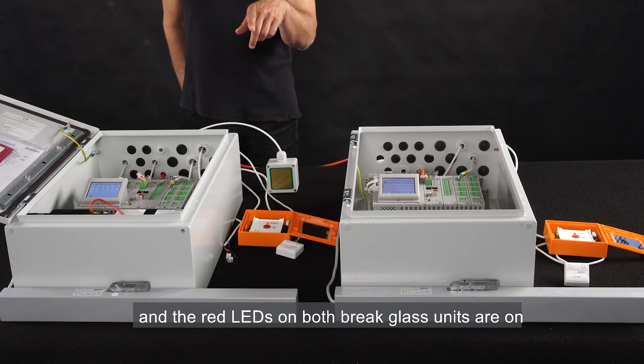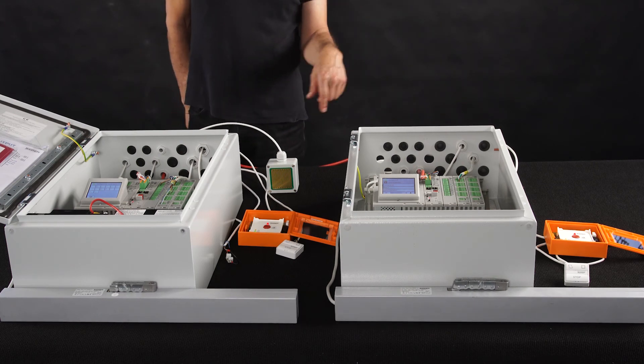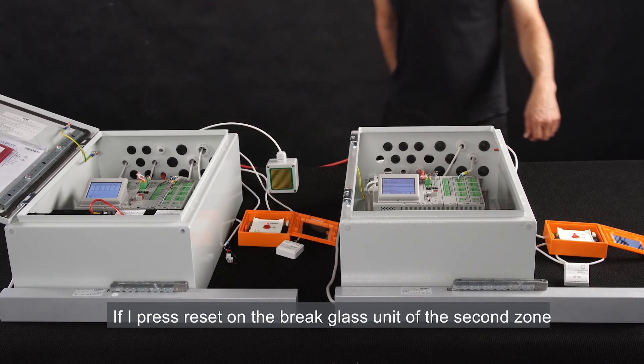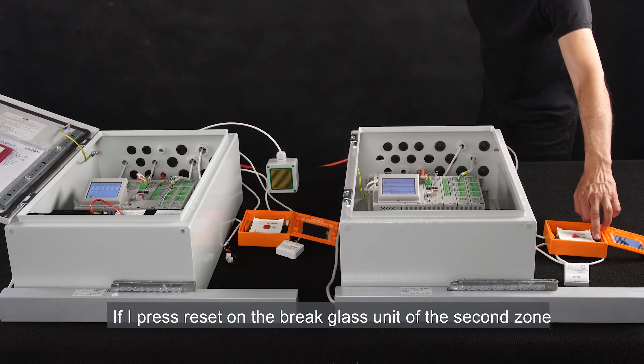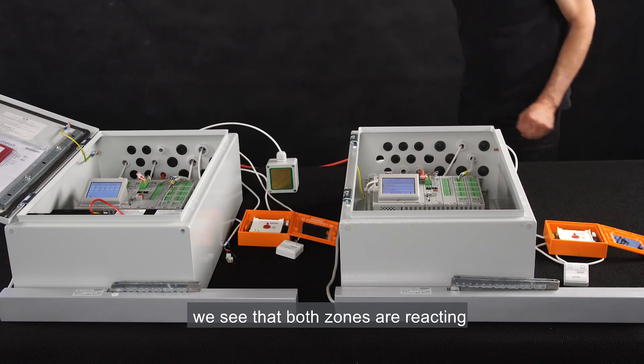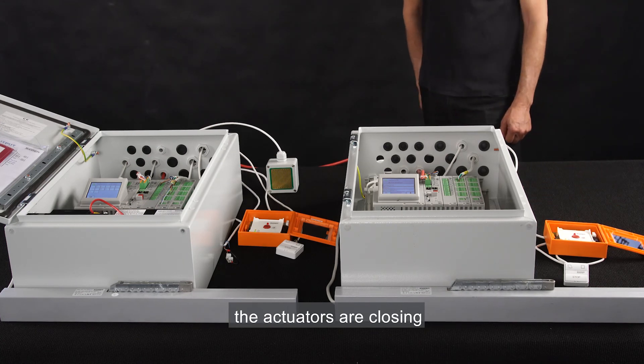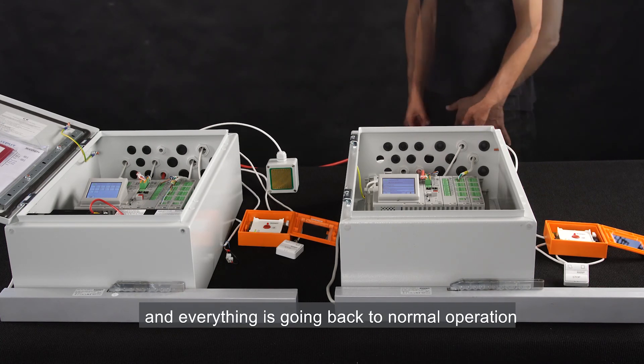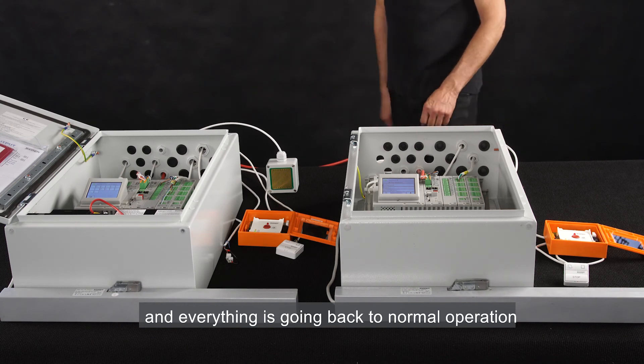If I press RESET on the break glass unit of the second zone, we see that both zones are reacting. The actuators are closing, and everything is going back to normal operation.